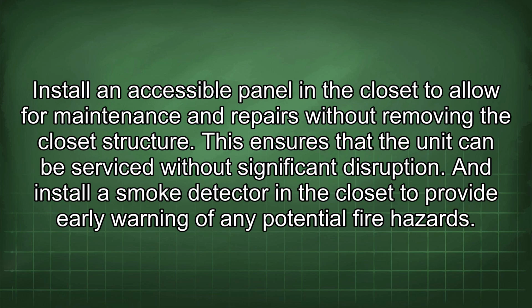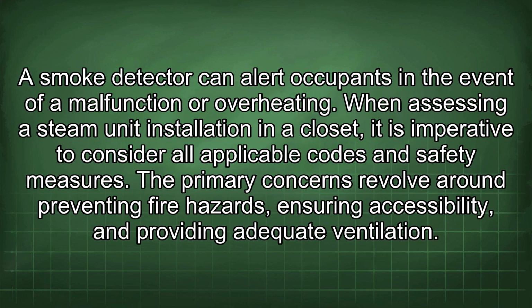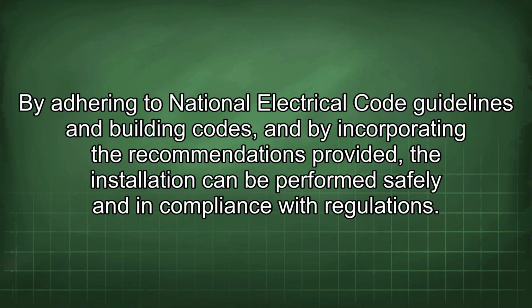Install an accessible panel in the closet to allow for maintenance and repairs without removing the closet structure. This ensures that the unit can be serviced without significant disruption. And install a smoke detector in the closet to provide early warning of any potential fire hazards. A smoke detector can alert occupants in the event of a malfunction or overheating. When assessing a steam unit installation in the closet, it is imperative to consider all applicable codes and safety measures. The primary concerns revolve around preventing fire hazards, ensuring accessibility, and providing adequate ventilation. By adhering to National Electrical Code guidelines and building codes, and by incorporating the recommendations provided, the installation can be performed safely and in compliance with regulations.